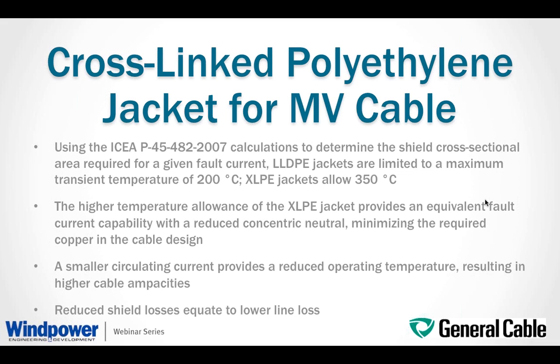With the XLPE jacket and its better heat deformation, the same neutral can go to much higher temperature without damaging the cable, as was demonstrated in the thermomechanical testing. So the higher temperature allowance of the XLPE jacket provides an equivalent current capability with a reduced neutral, minimizing the required copper in the cable design. And in turn, a smaller neutral means higher shield resistance, which means smaller circulating current in the metallic shield. That may help reduce the operating temperature, have a positive impact on the resulting ampacity of the cable, and reduce the losses in the metallic shield.